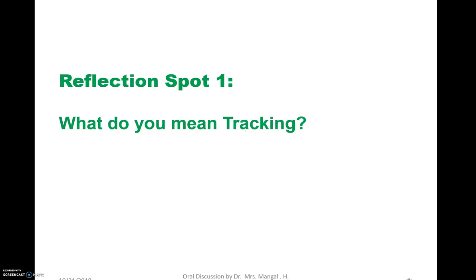Now before starting, I want to ask you one simple question — a reflection spot question. Think about it and write down your answer: what do you mean by tracking? Because unless you know what tracking or tracks are, you cannot understand what tracks are developed, how they are developed, and what their significance is. Track — the name itself implies it. Track means a road, a path — a path for conduction, a path for sparking. So tracking is the phenomenon of development of a permanent conducting path in the insulating material. It is a process and a very long process, but since we are applying very high voltage it can develop immediately.